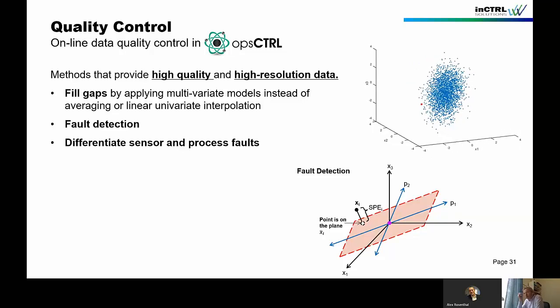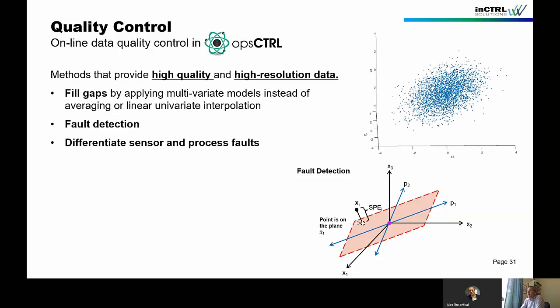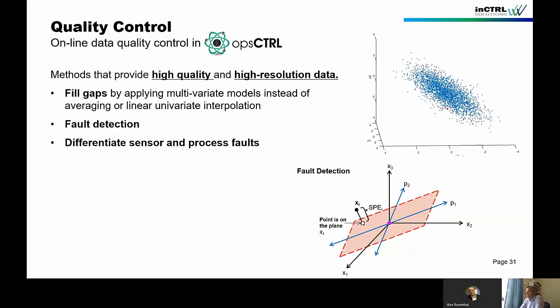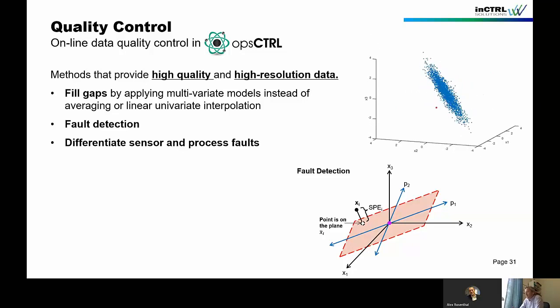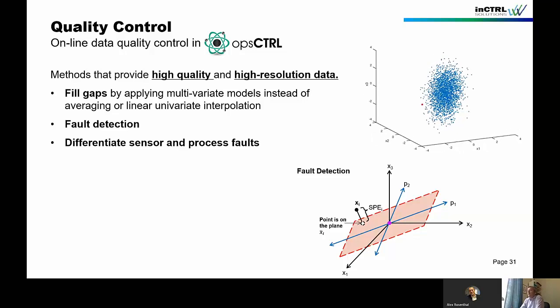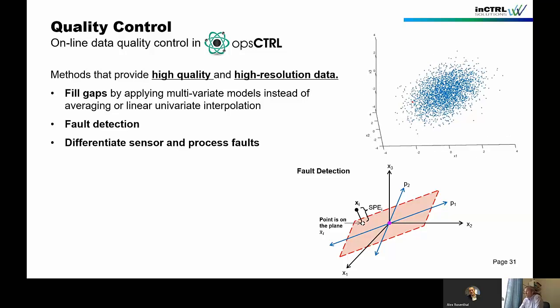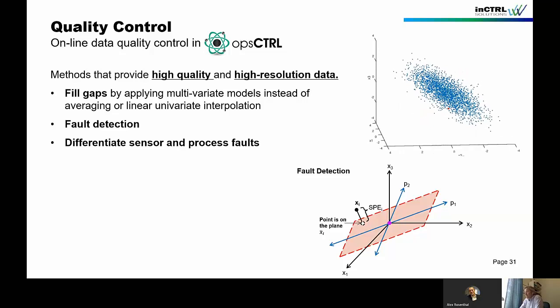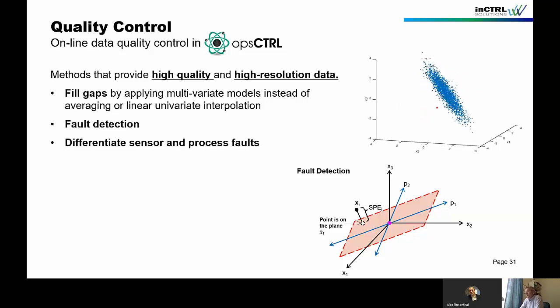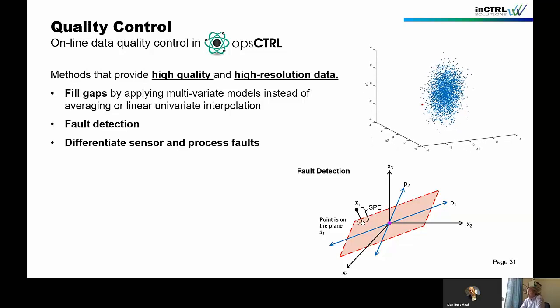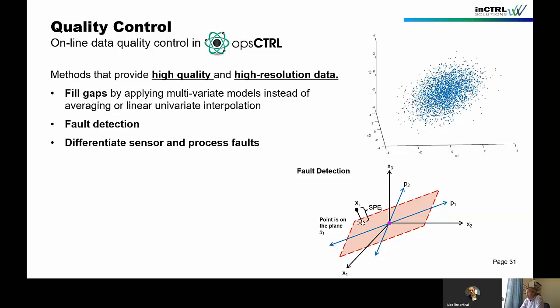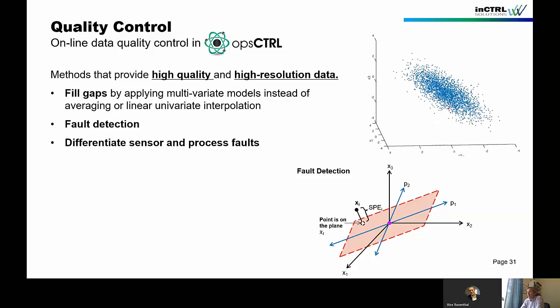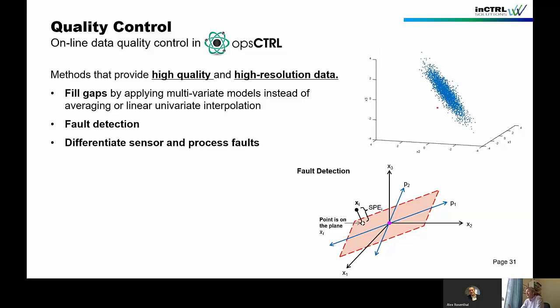One of the critical points is actually to differentiate sensor and process faults. Right? So sensor faults mean that you don't want to have that entering your system. You want to exclude that, replace that maybe. And then you have process faults, and that's actually what you're interested in. Right? So you need to know if there's something wrong, so you cannot exclude process faults. So the tricky bit is how do you differentiate that? And we do that by using multivariate models, and that's highly simplified, of course.